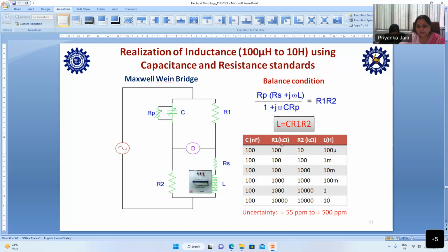For 100 microhenry, we have some combination of R1, R2 like this. 100 microhenry to 10 henry we are defining in terms of capacitance and reactance, capacitance and resistance. The uncertainty we are getting for inductance standard is 55 ppm to 500 ppm for our standards, and for customers we are providing around 100 ppm for the 1 millihenry, 10 millihenry and 100 millihenry range. And for higher values of inductor, the uncertainty is a little bit higher.